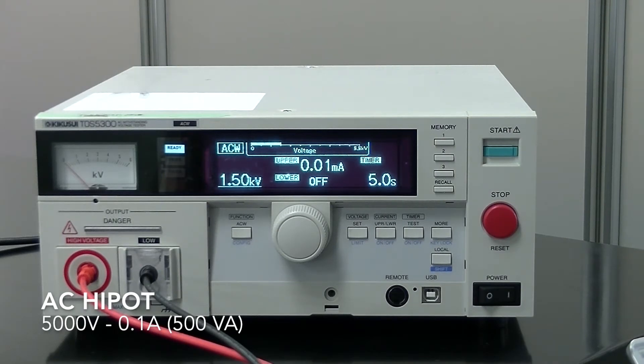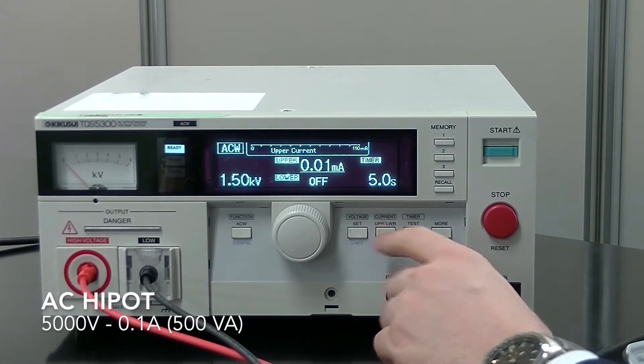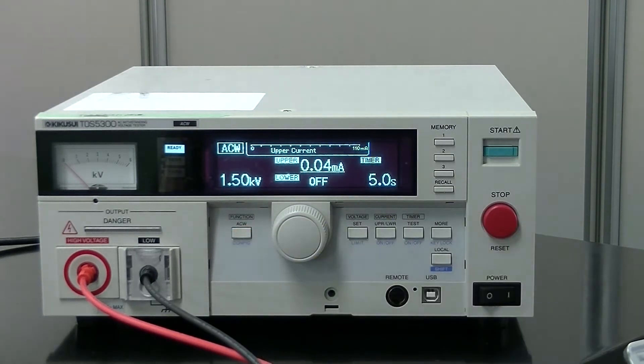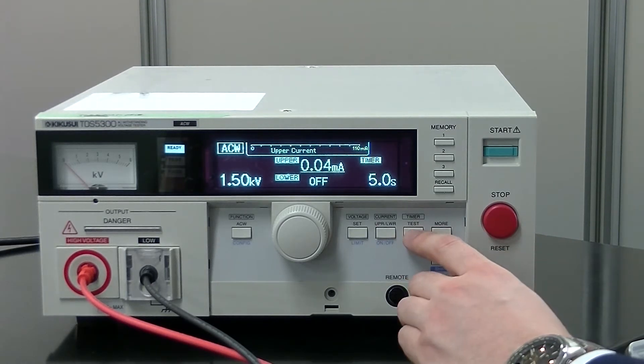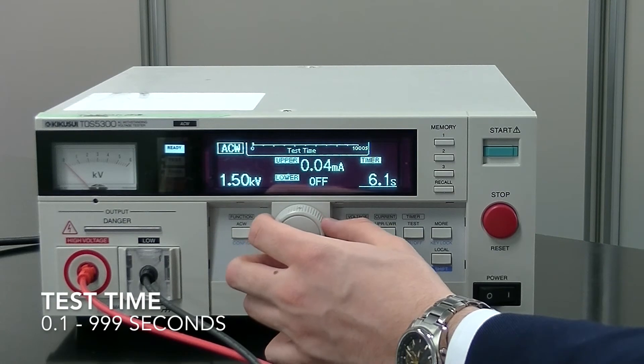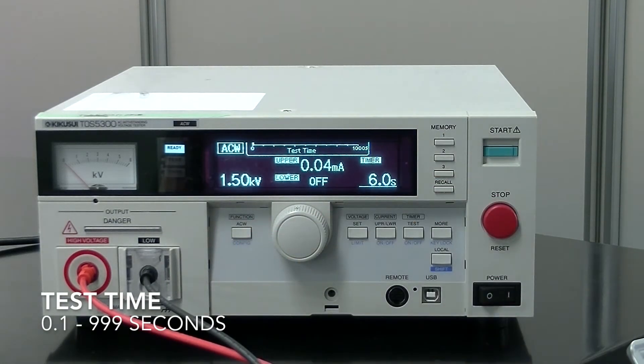Next, you can set the upper current levels by pressing the current button and moving the dial in the same way. Let's go 0.04 milliamps. The last setting you need to consider is your timer. This is done by pressing the timer button and moving the dial. Let's go 6 seconds.